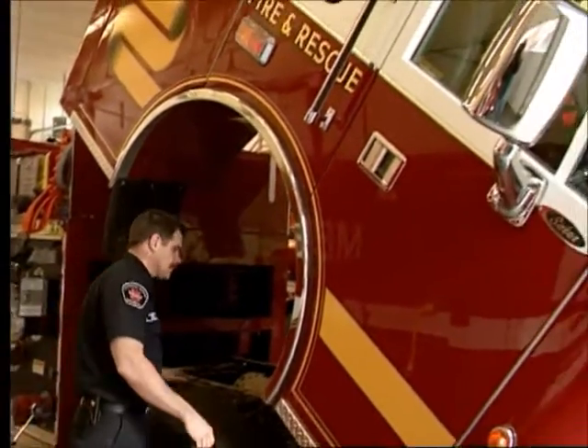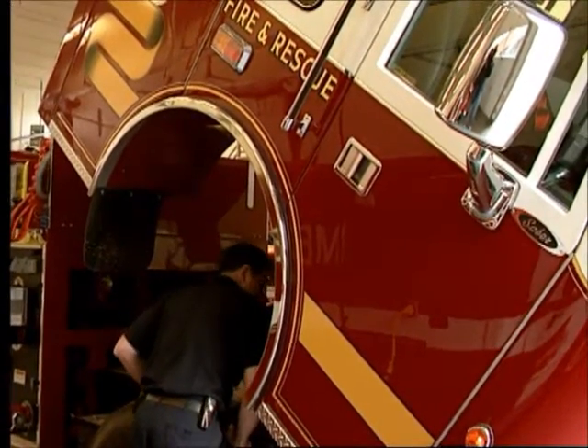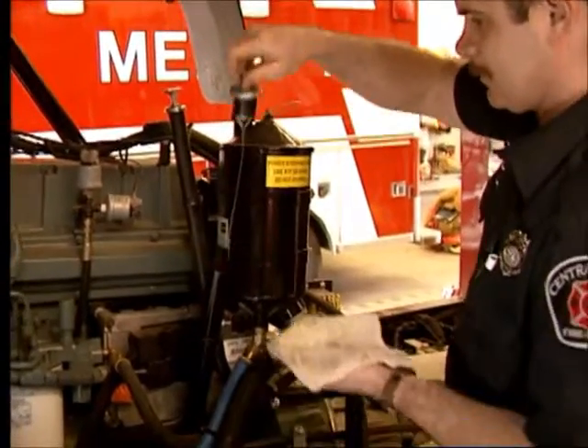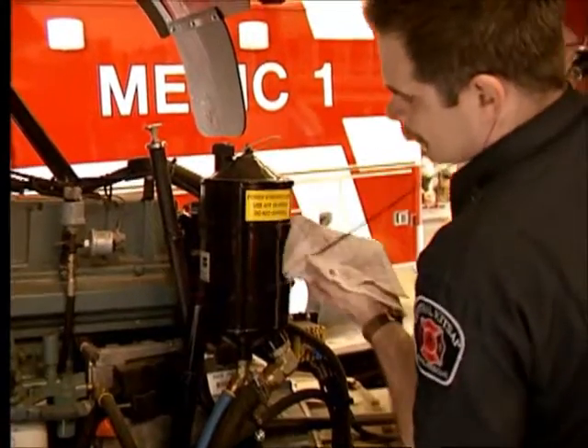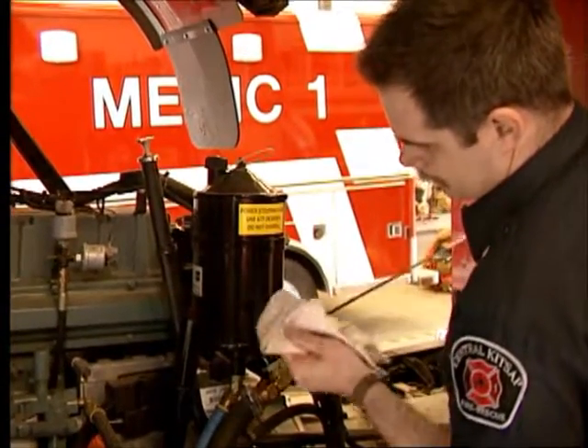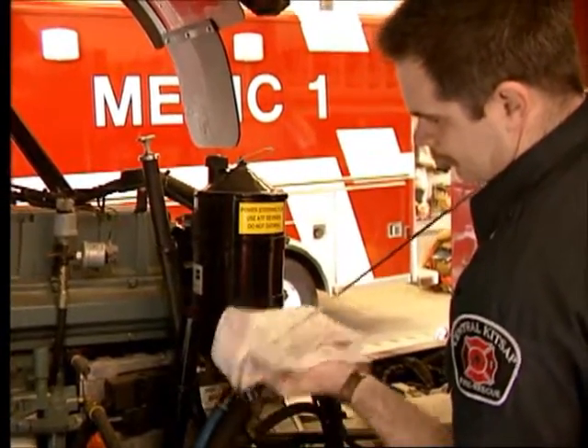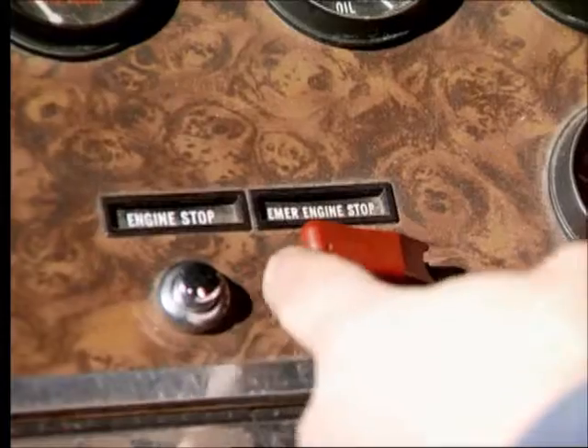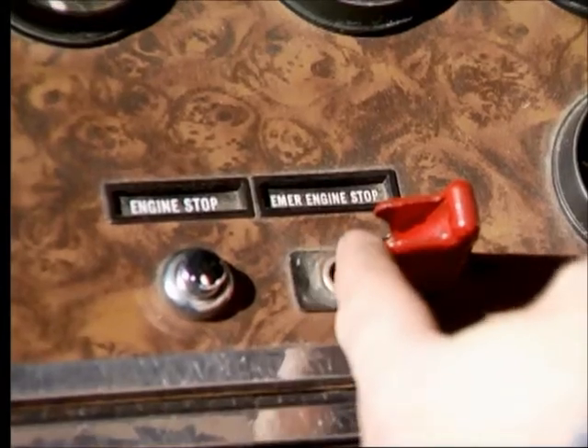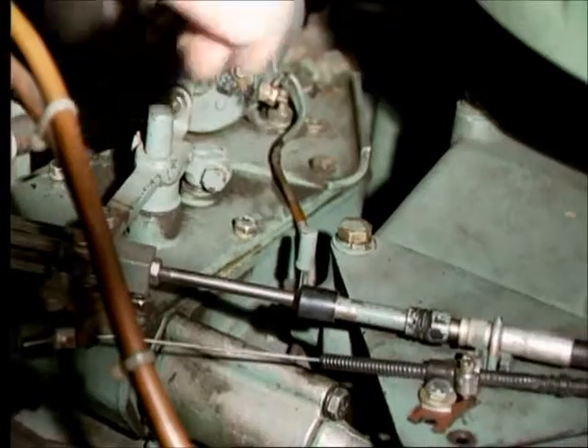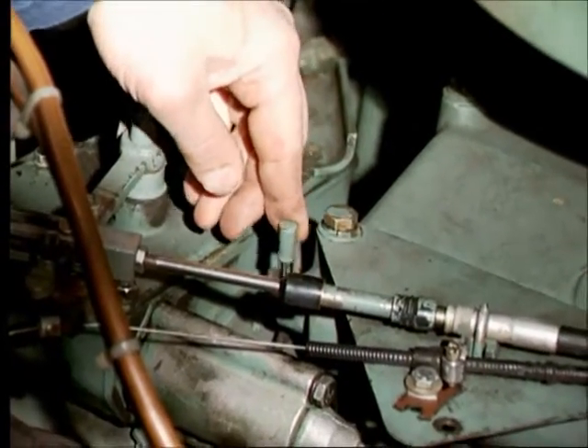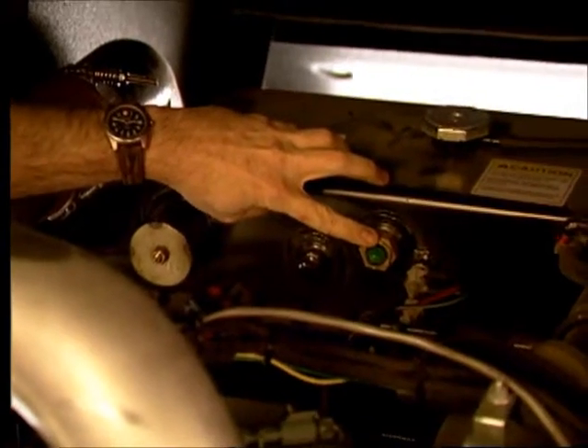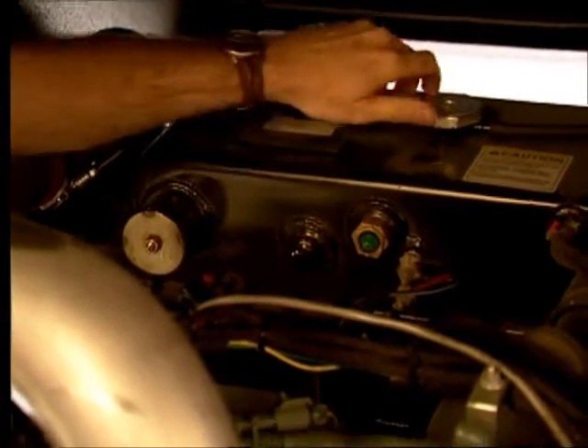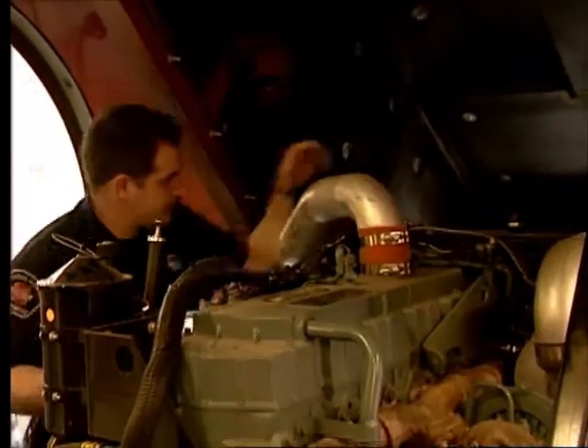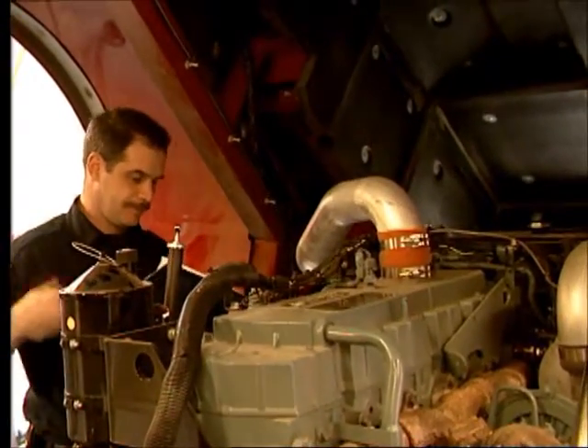Continue the daily inspection by looking inside the engine compartment. Begin by checking the crankcase oil to make sure it is at the proper level. If the oil level is low, add oil. Check the air filter. If you have a diesel engine, check the emergency shutdown switch and manual reset to make sure it is working properly. Check the level of the coolant in the radiator. If the level is below the fill line, additional coolant will need to be added.